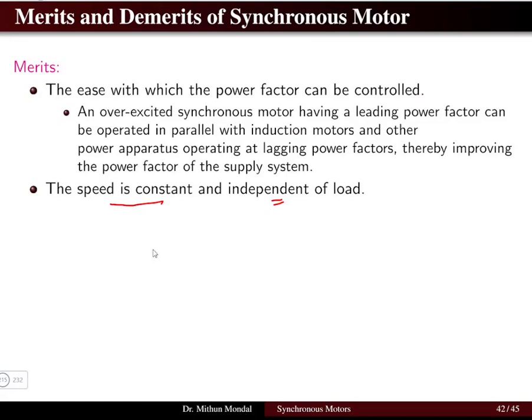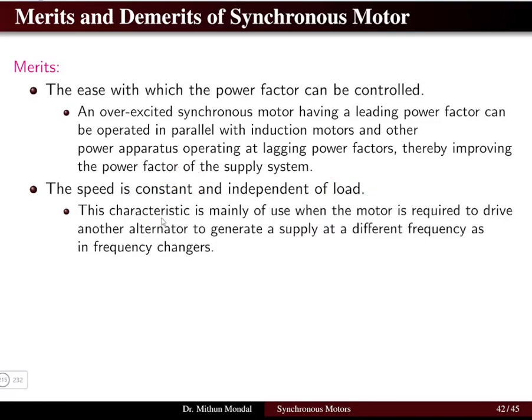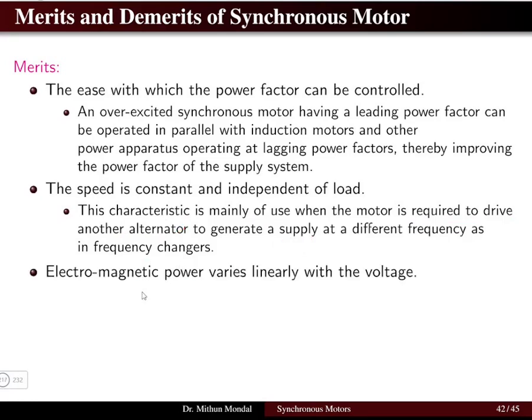The second merit is that the speed is constant and independent of the load. The synchronous motor operates at a particular synchronous speed determined by the supply frequency. Even with variation in load, speed remains constant. This characteristic is especially useful when the motor is required to drive another alternator to generate a supply at a different frequency — functioning as a frequency changer.